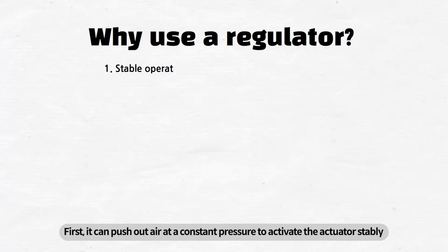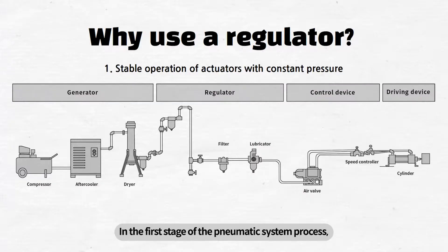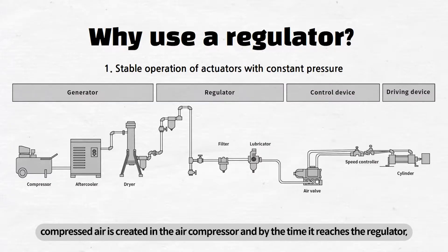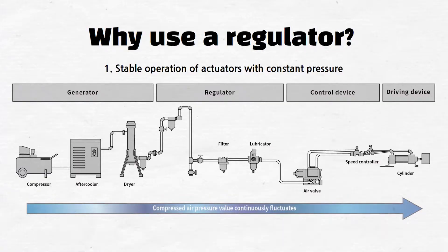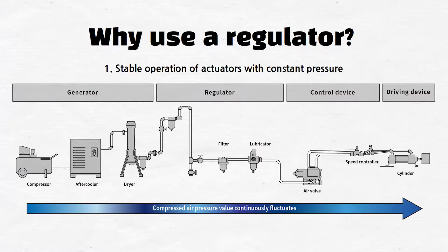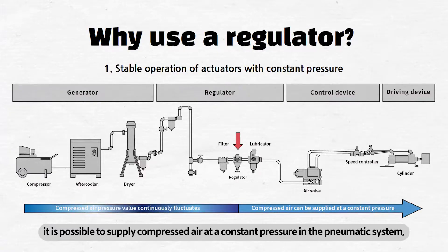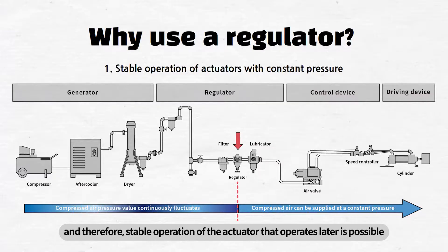First, it can push out air at a constant pressure to activate the actuator stably. In the first stage of the pneumatic system process, compressed air is created in the air compressor, and by the time it reaches the regulator, the compressed air pressure is not constant but constantly changes while passing through various processes. By installing a regulator, it is possible to supply compressed air at a constant pressure in the pneumatic system, and therefore, stable operation of the actuator that operates later is possible.